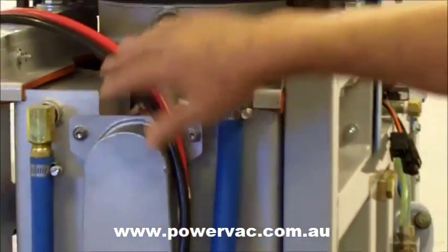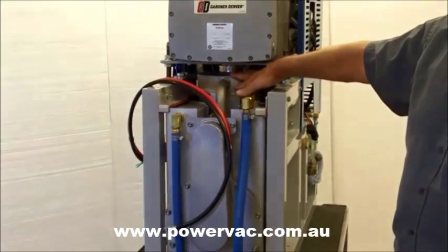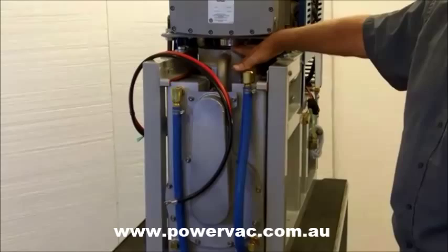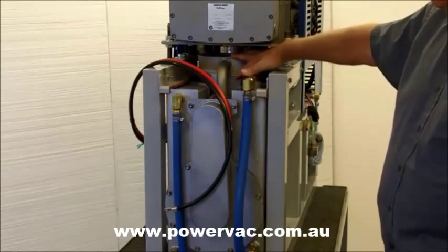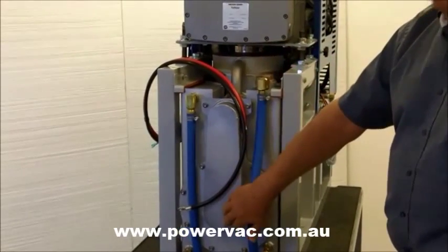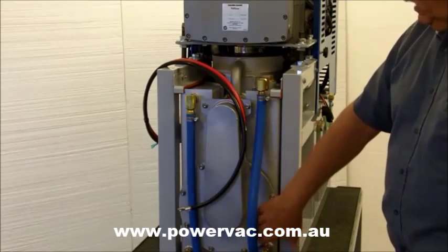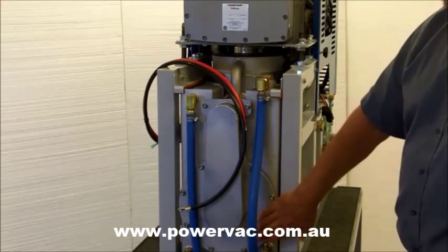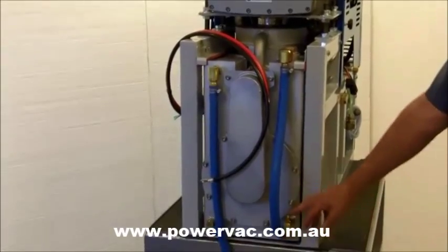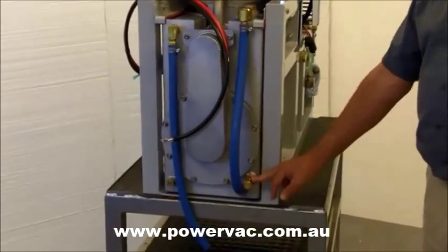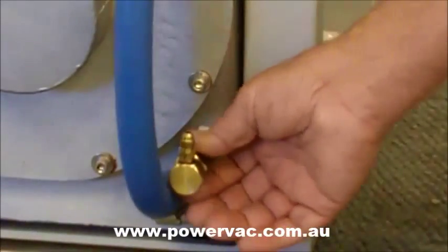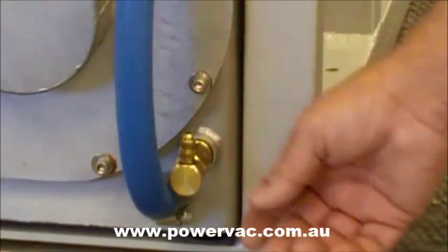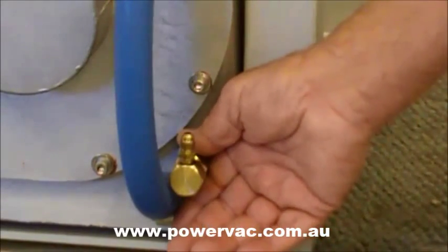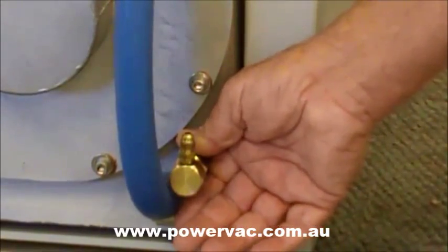Back here is where the exhaust comes out of the silencer, which is in here under the blower, both the blower silencer and the engine muffler. Exhaust gases travel down through this piece and into the heat exchanger, which is the round unit at the bottom. Over here on this side is a thermal relief valve for the water box. This is connected to the waste tank. Its purpose is to keep water box temperatures under 165 degrees.